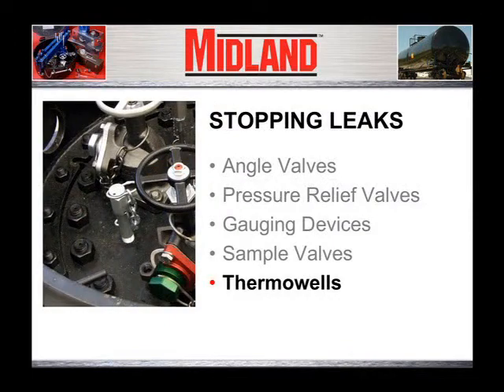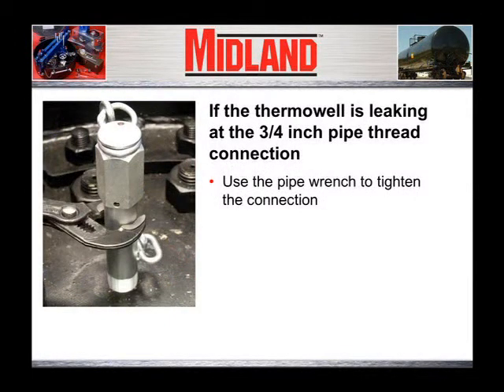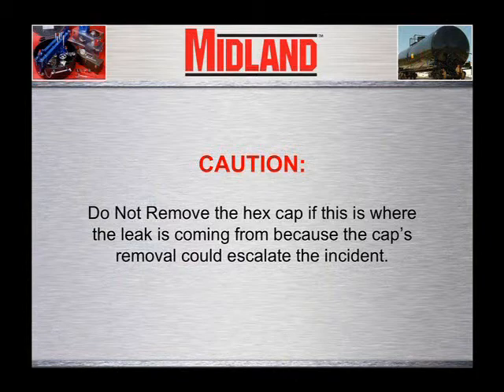Next, we will examine stopping leaks from thermowells. If the thermowell is leaking at the three-quarter inch pipe thread connection on the cover plate, use the pipe wrench to tighten the connection. Another potential leak path is below the hex cap at the top of the fitting; further closing of this cap may stop the leak. Do not remove the hex cap if this is where the leak is coming from, because the cap's removal could escalate the incident.